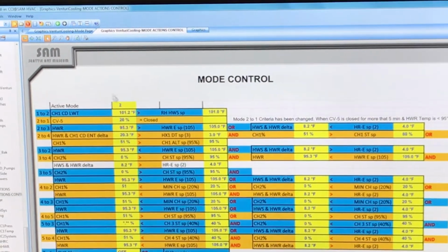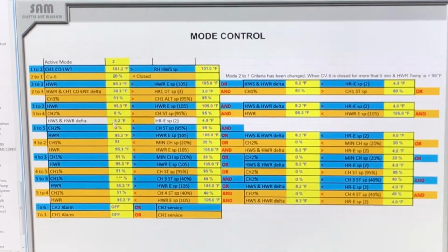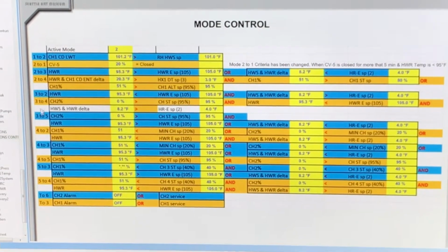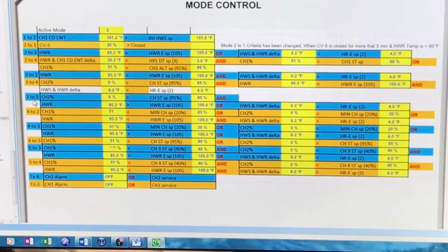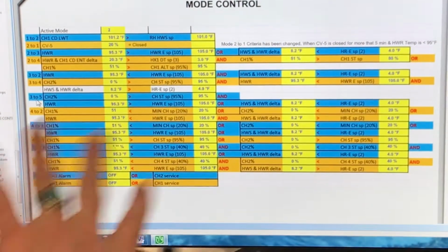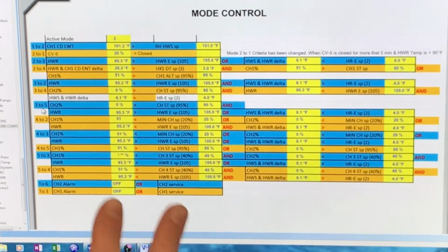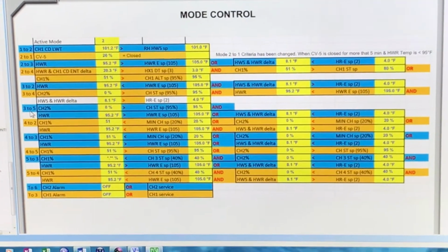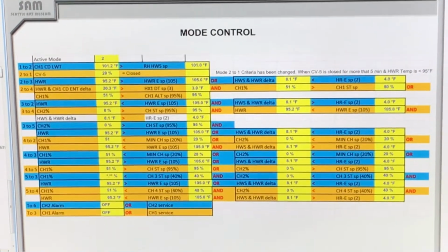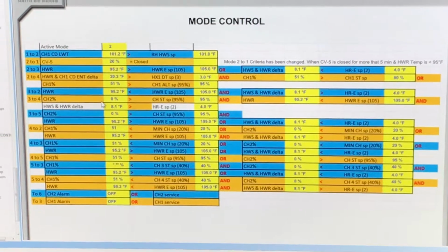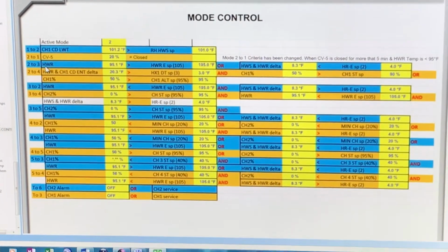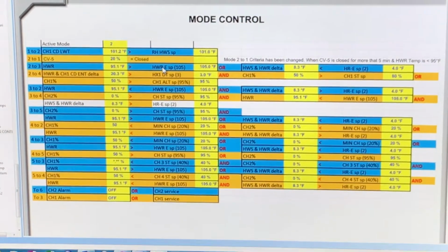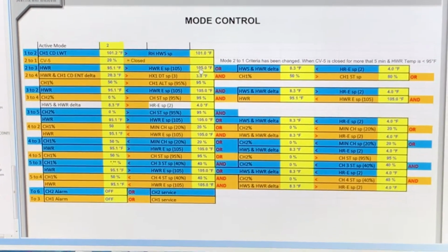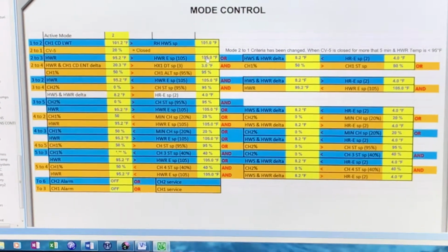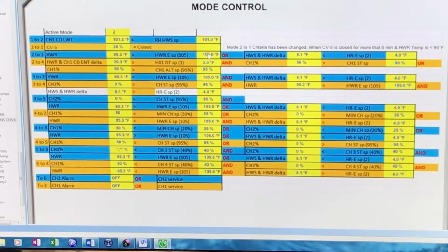Yep. The same scenario goes for the rest of these mode controls. This has to be in 3, like Sam was saying, for these to happen. If you wanted to move into a certain mode and you override it, these might not be true. Just because you override a mode doesn't mean the ands are magically going to happen. It'll just be in that mode because you overrode it. Just priority. Overriding is only for emergencies. So if you actually wanted to change it to a different mode, you would make these happen. Like if we wanted to go from mode 2 to 3, our hot water return has to be greater than 105, so we could lower this 105 to 90 and it would change to mode 3 without being overridden. Got it.